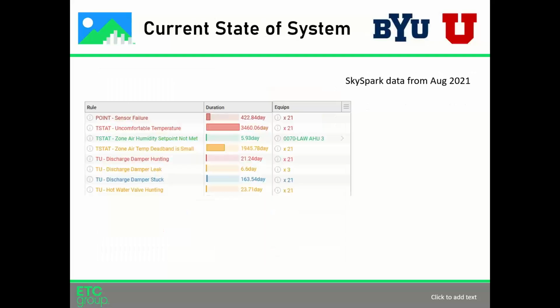When we started this process, we were very focused on what you'd think, since the thermal loop wasn't charging, you go stand in the mechanical room and look for an issue there. Things like that made sense, like an end switch not functioning on a valve, so you replace the end switch, or a flow meter not working, so you replace it.